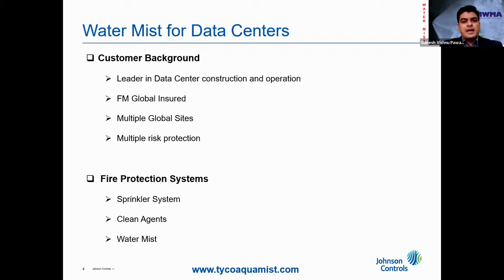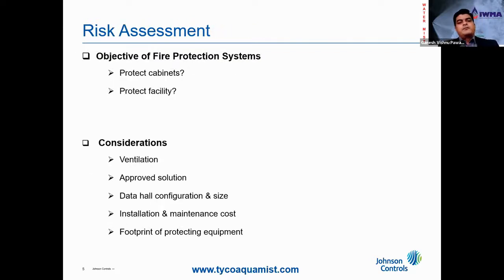As per FM, data centers can be protected either with a sprinkler system, a clean agent, or a water mist solution. But before selection of any fire protection system, it is necessary that we know the prime objective of the system, whether it is to protect the cabinets or to protect the facility. At the same time, we need to take into consideration a few key parameters such as ventilation, whether we need to shut down the ventilation unit, whether the solution is approved by a recognized party, the configuration of the data hall, what is the size, how big is the data center facility, the installation and maintenance cost associated with it, the footprint of the protecting equipment, and what kind of infrastructure it requires to keep this equipment.